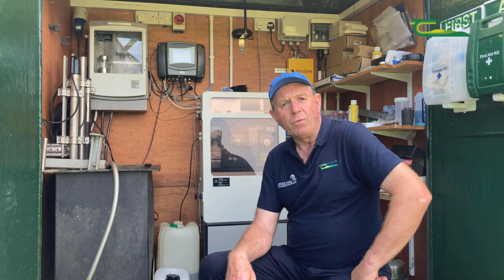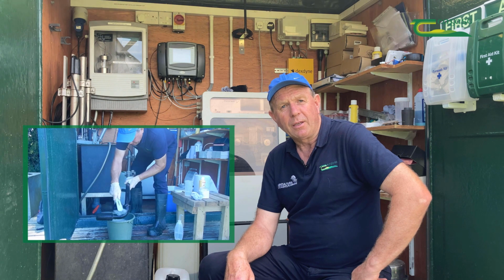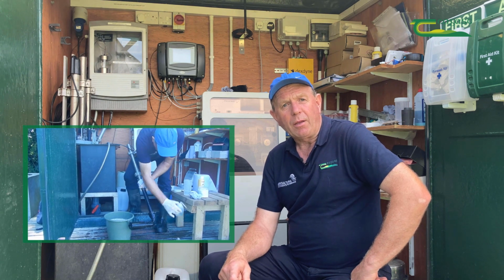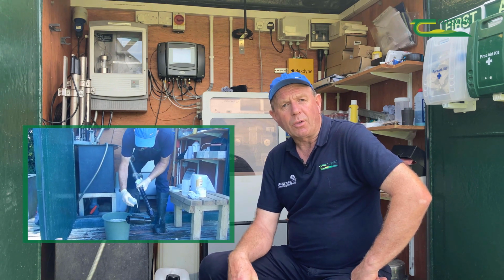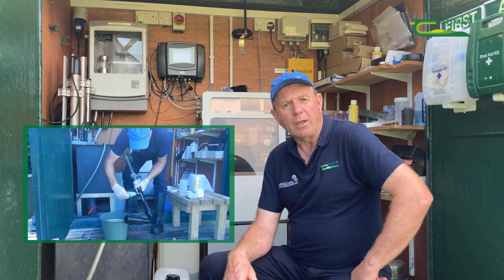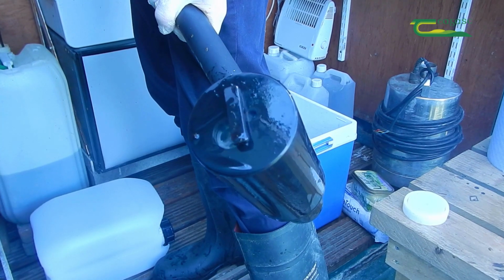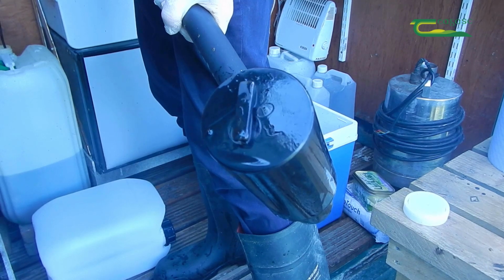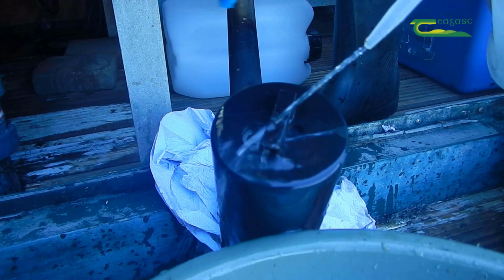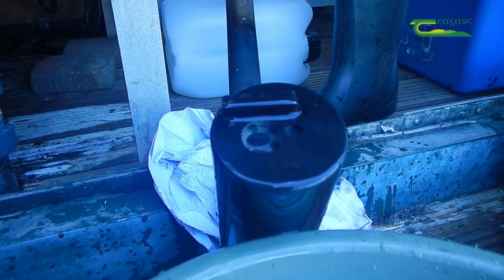Next up is the Turbidity Probe, and again I will remove the Turbidity Probe from the tank. Again, clean it down, any dirt or whatever's on the probe, give it a good cleaning down. Operate the wiper on the probe and use maybe an old toothbrush again with deionized water to clean in behind the wiper blade.